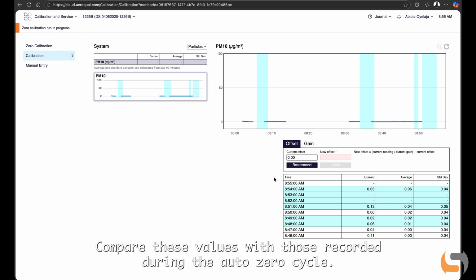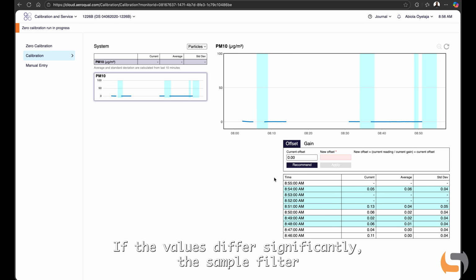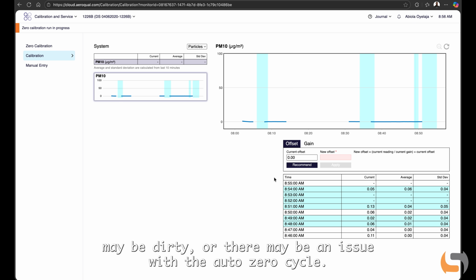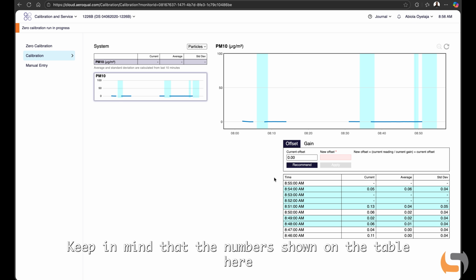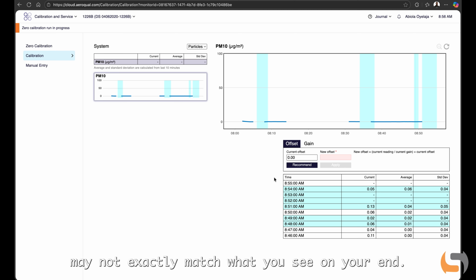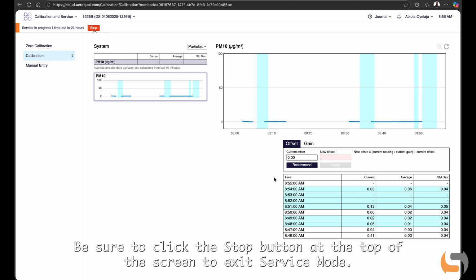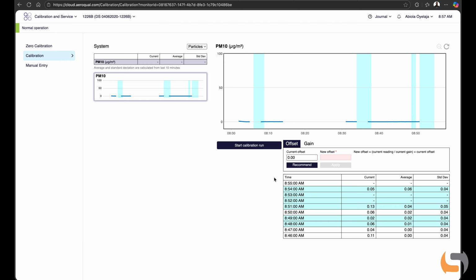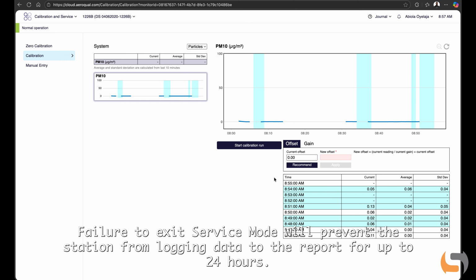If the values differ significantly, the sample filter may be dirty or there may be an issue with the auto zero cycle. Keep in mind that the numbers shown on the table here may not exactly match what you see on your end. Be sure to click the Stop button at the top of the screen to exit service mode. Failure to exit service mode will prevent the station from logging data to the report for up to 24 hours.